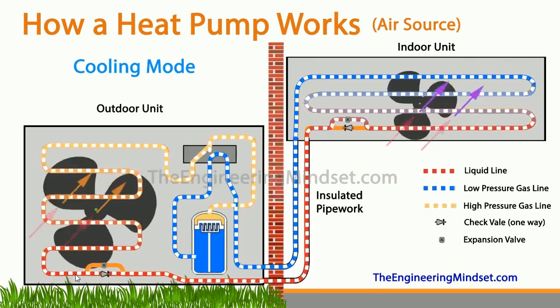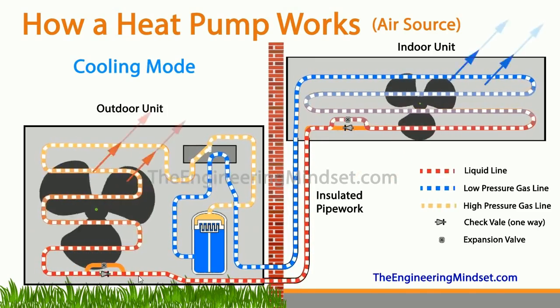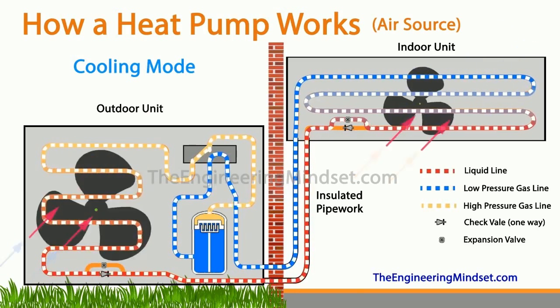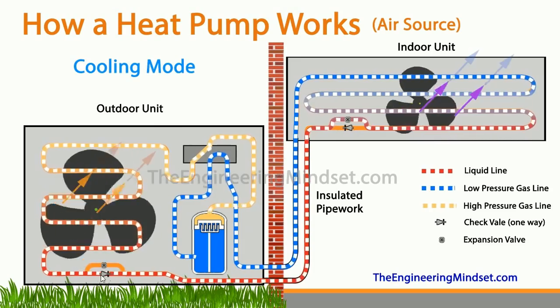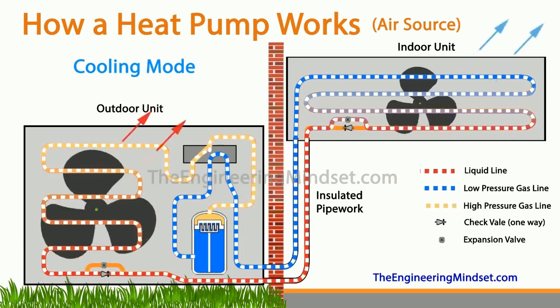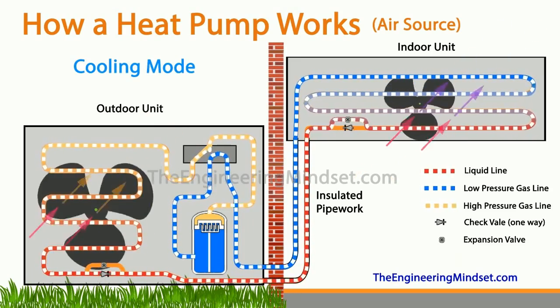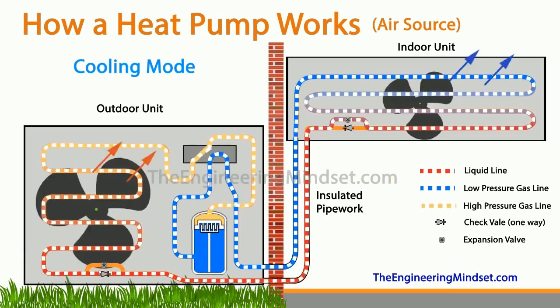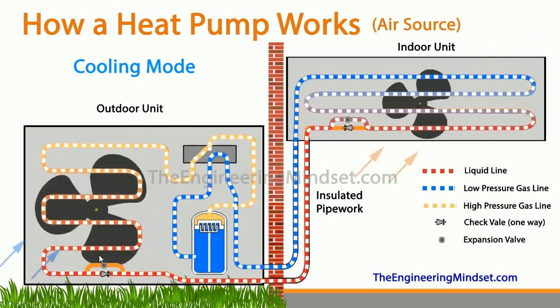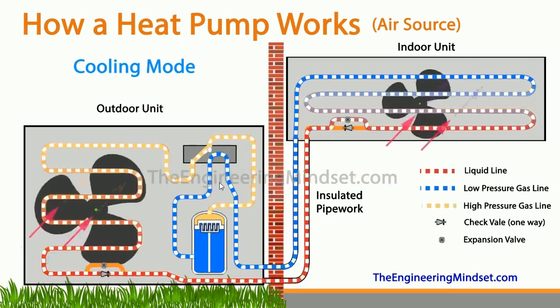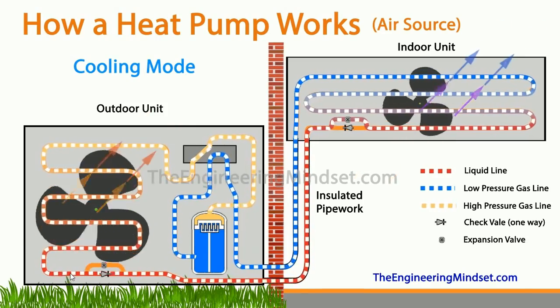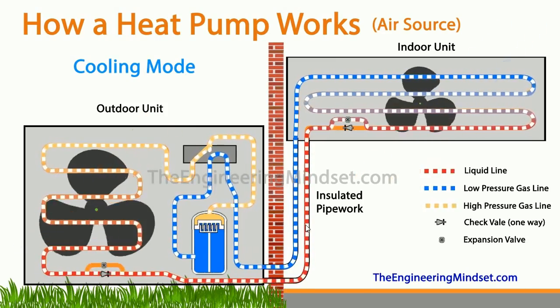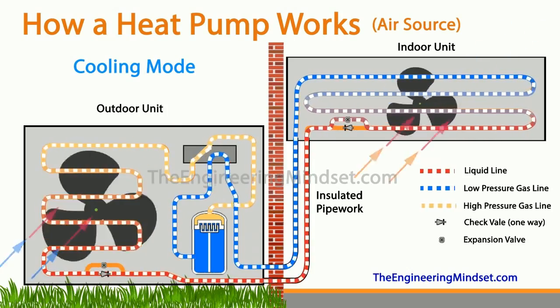So when the refrigerant leaves here and passes through this check valve, it will be a high pressure, medium temperature saturated liquid. And the force of all the refrigerant behind it coming out of this compressor is what's pushing that refrigerant all the way around and to the other components in this system.